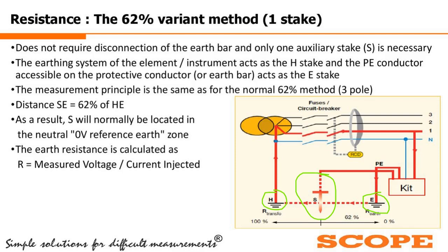Now, this measurement principle is the same as the normal 62% method, meaning the distance SE, that is S to E, should be around 62% of the total distance HE. Hope I could make it clear. That's the reason it is called the 62% method. As we have mentioned over here, distance SE equals 62% of HE. This is the rough thumb rule we are talking about as the 62% method. As a result, S will normally be located in a neutral zero voltage reference earth zone. So this is how the earthing voltage is distributed, and we get a zero volt earth reference zone roughly at 62%.